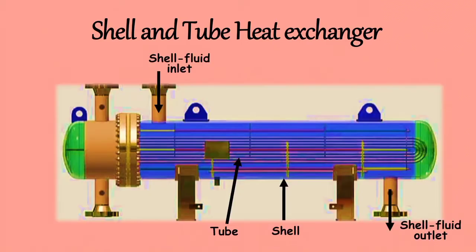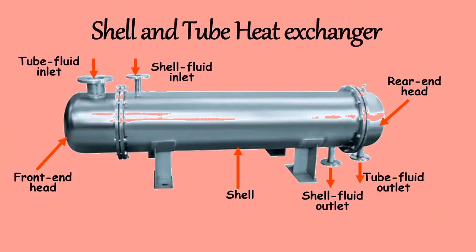The next component is the front end head and rear end head. These are used for the entrance and exit of the tube fluid. The front end head is stationary, while the rear end head could be either stationary or floating, depending on the thermal stresses between the tubes and shell. The selection criteria for the front end head are mostly based on cost of the heat exchanger, maintenance and inspection, hazard due to mixing of shell and tube fluids, and leakage to ambient and operating pressures.